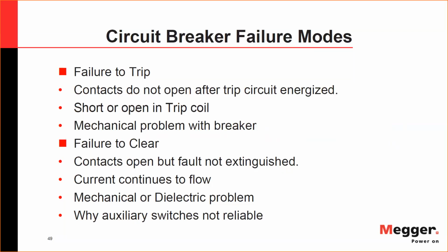In any case of this, it is very important to see if the current is still flowing or not after issuing the trip command and the circuit has operated. That's why the current detector stage or element is very important when you are talking about circuit breaker failure protection.